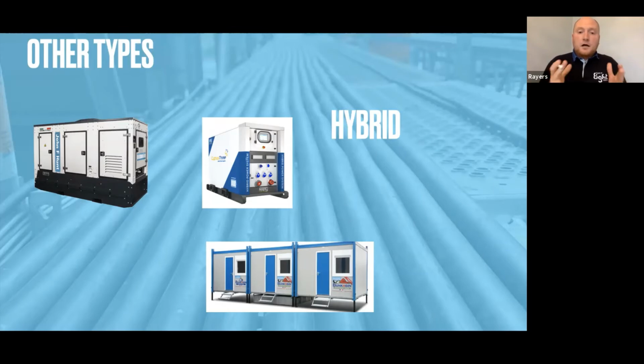What you can do is put a hybrid unit in place alongside a generator, and use the generator to charge that battery and also deliver the hit of power that's needed at those peak points. For the rest of the time, the battery will just take the load. In terms of fuel savings, it's really quite remarkable what you can do, especially over long periods of time. Where they come unstuck slightly at the moment is that hybrid units are incredibly expensive to buy and therefore incredibly expensive to rent. So we're not quite there yet with the economies of it all, but the principle I think is really exciting.